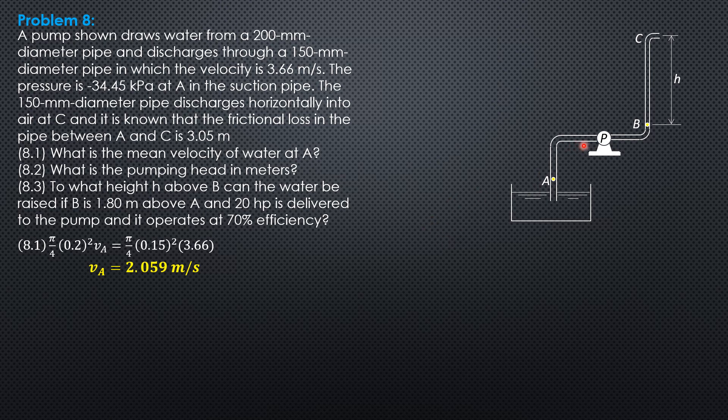The pump operates with an output power of efficiency times 20 horsepower and it is equal to weight flow rate Q times gamma of water pumping head divided by 746. If we express Q in cubic meter per second, gamma in newtons per cubic meter and of course pumping head meters.